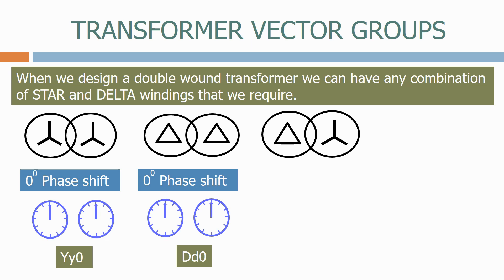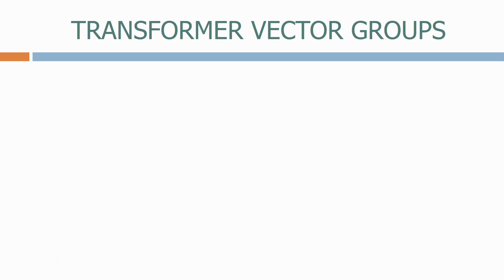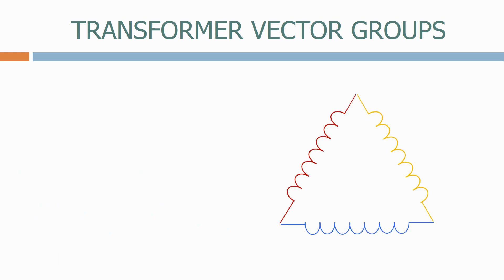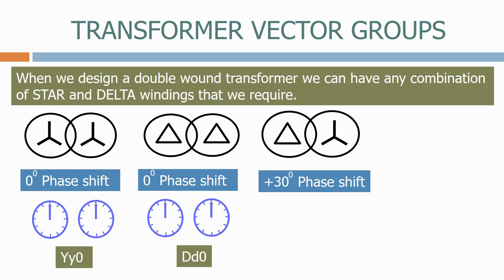Let's now look at a delta-star transformer. Because of the physical arrangement of a delta-star transformer and the way the vectors are arranged, we naturally get a plus 30-degrees phase shift from the primary to the secondary winding, as shown on this diagram. If we show the delta winding, then superimpose the star winding over the top and measure the phase angle, we'll see the difference is 30 degrees. Therefore, on the clock faces, the secondary winding is shown at 11 o'clock. This is represented in the symbol as Dy11.